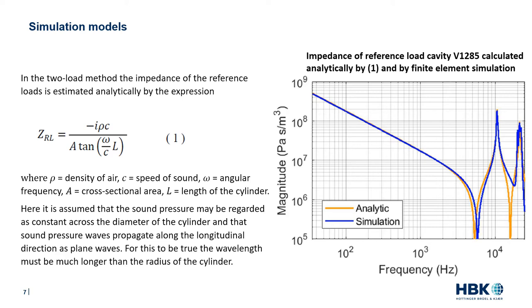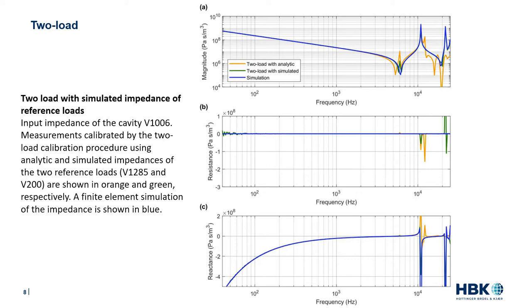We have therefore replaced the analytical expression with finite element simulation models of all reference load cavities. To illustrate the effect, we calibrate a measurement of cavity 1006 cubic millimeters using both analytical and simulated impedances of the two reference loads — 1285 and 200 cubic millimeters. The blue trace is the reference result from simulation. Using the analytical expression produces a relatively large error in magnitude around the first minima and above the first maxima. The two-load method with simulated impedances still generates a small error at the minima and a negative resistance around the maxima.